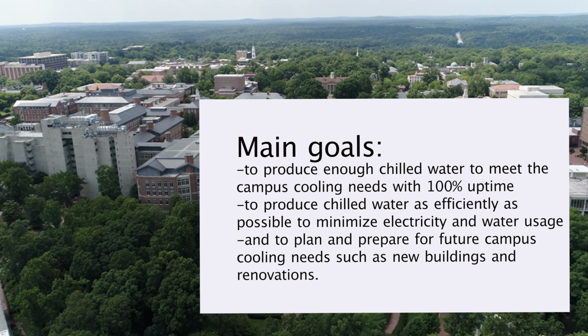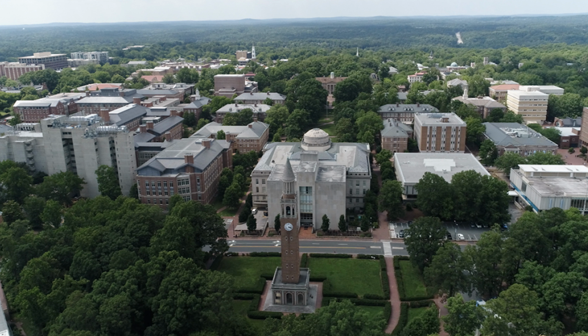The main goals of chilled water systems are to produce enough chilled water to meet the campus cooling needs with 100% uptime, to produce chilled water as efficiently as possible to minimize electricity and water usage, and to plan and prepare for future campus cooling needs such as new buildings and renovations. In order to understand the chilled water process, let's look at the whole process in 3 cycles. The chilled water cycle, refrigerant cycle, and condenser water cycle. All 3 cycles are completely separate, only connecting through heat that is transferred between them.